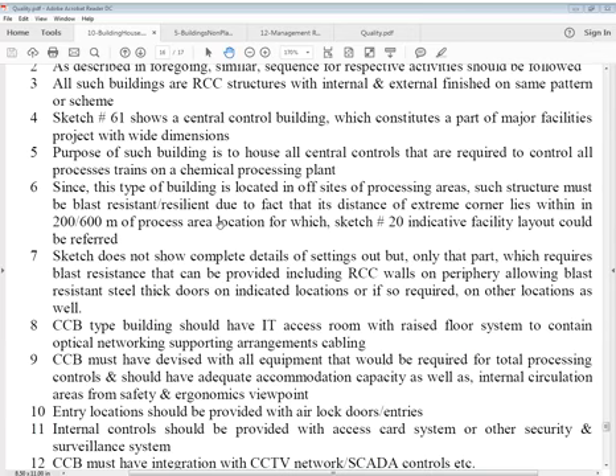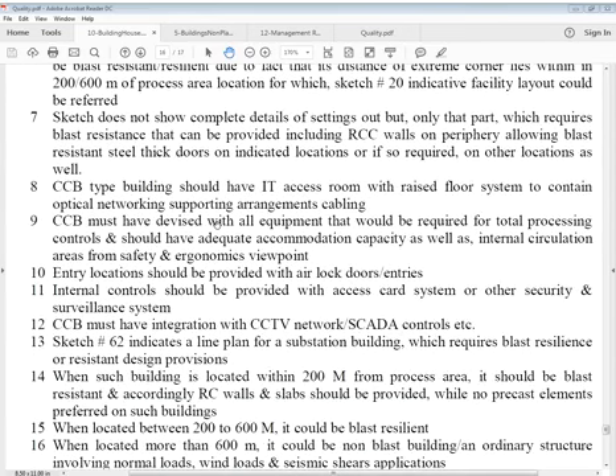Such a structure must be blast resistant or blast resilient depending on the distance - its extreme corner lies within 200 to 600 meters of the process area location, for which sketch number 20 indicates facility layout. The sketch doesn't show complete details of the setting out, but only the part requiring blast resistance, which can be provided including RCC walls on peripheral areas, allowing blast resistant steel thick doors at indicated locations, or other locations as required.